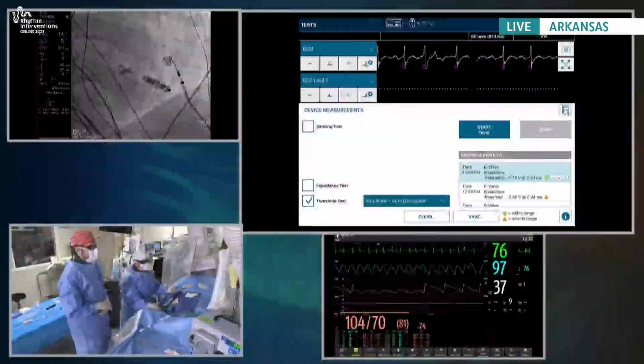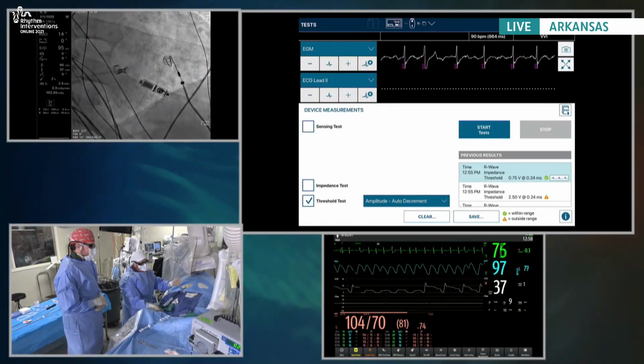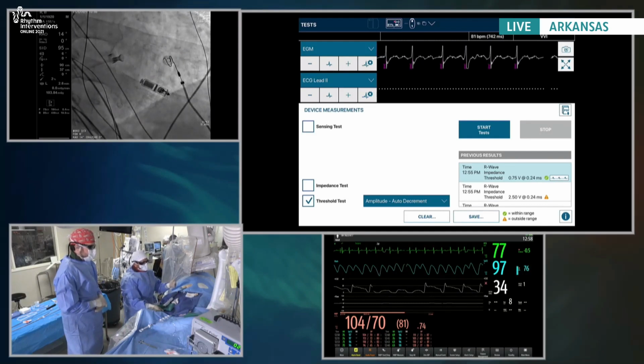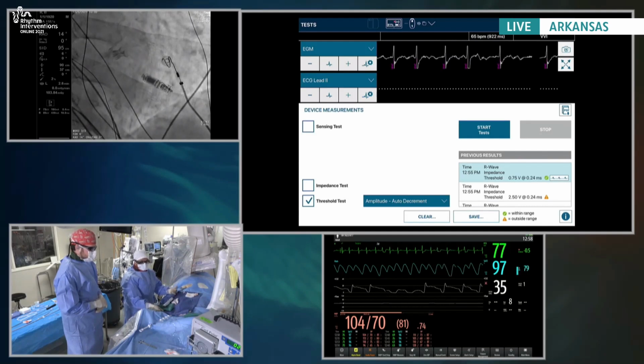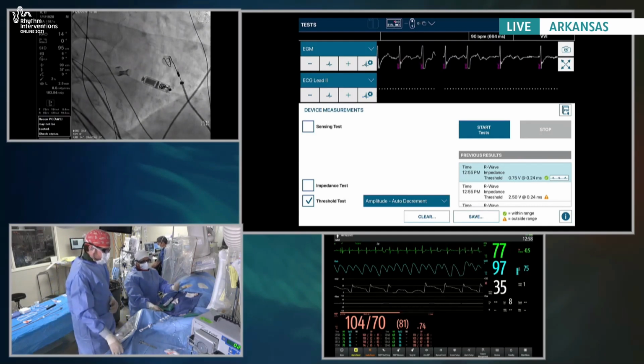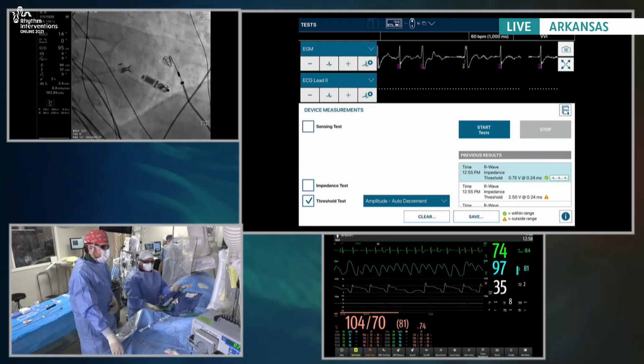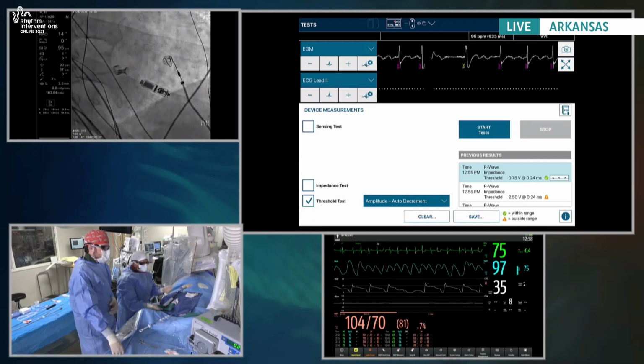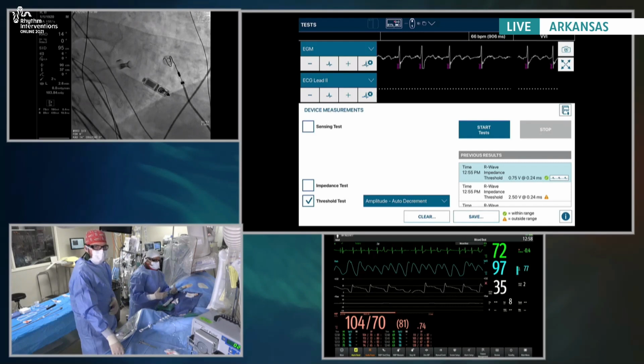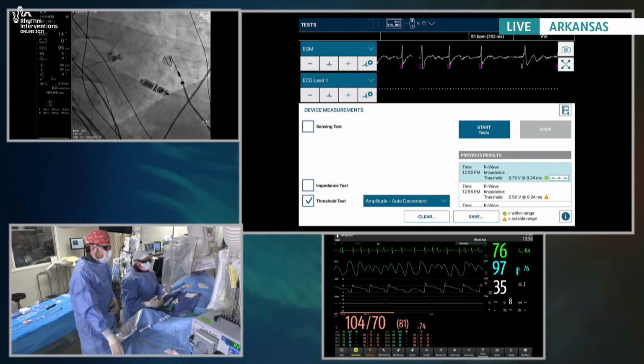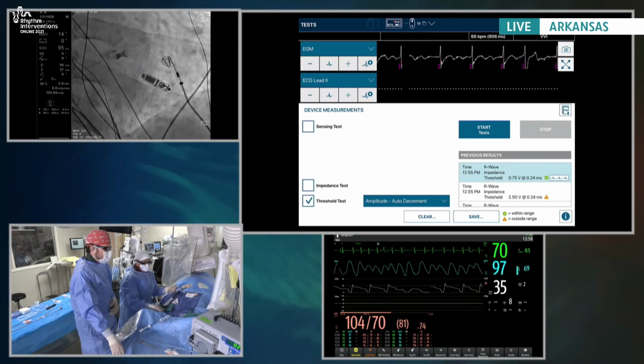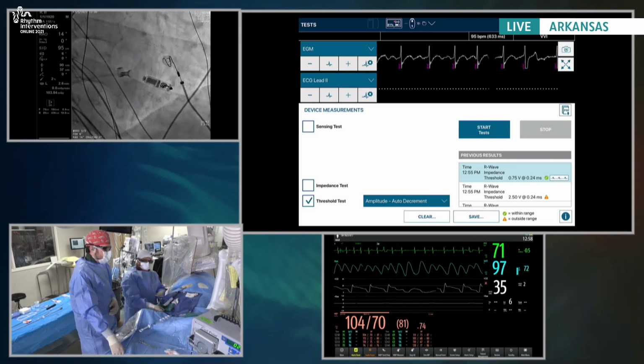Yep, agree. So the number one thing for me is I want to make sure that I see those at least 2 times engaged. So if there's contact, the device was septal, there were good R waves and the impedance is good, I'm okay to wait. And as long as the threshold's coming down, I'm okay to wait. All of the numbers have to kind of match up for me to take that whole waiting for the threshold to happen. If say the R waves are bad or the impedance is bad, then I'm not going to sit around and wait.